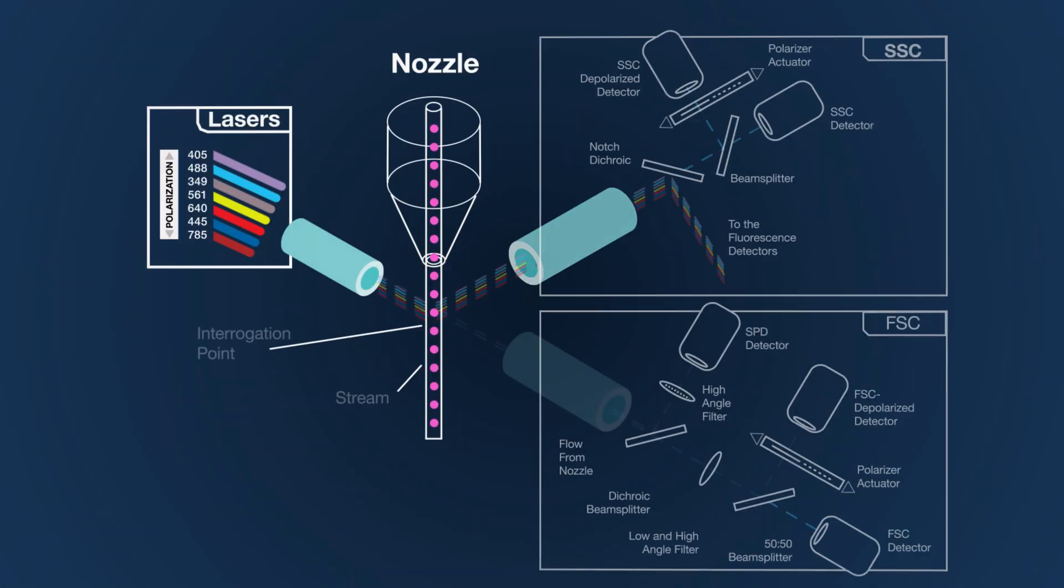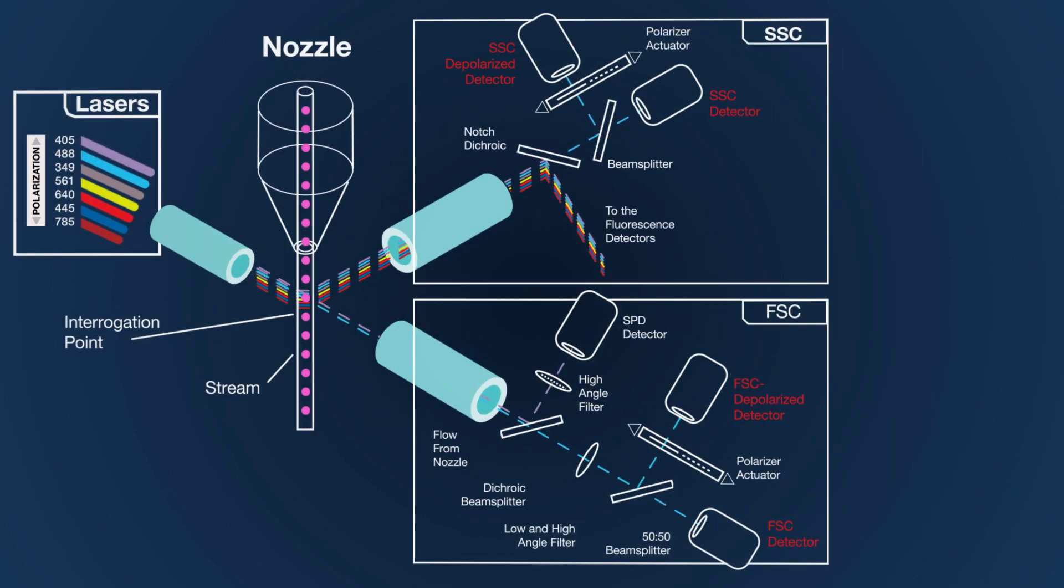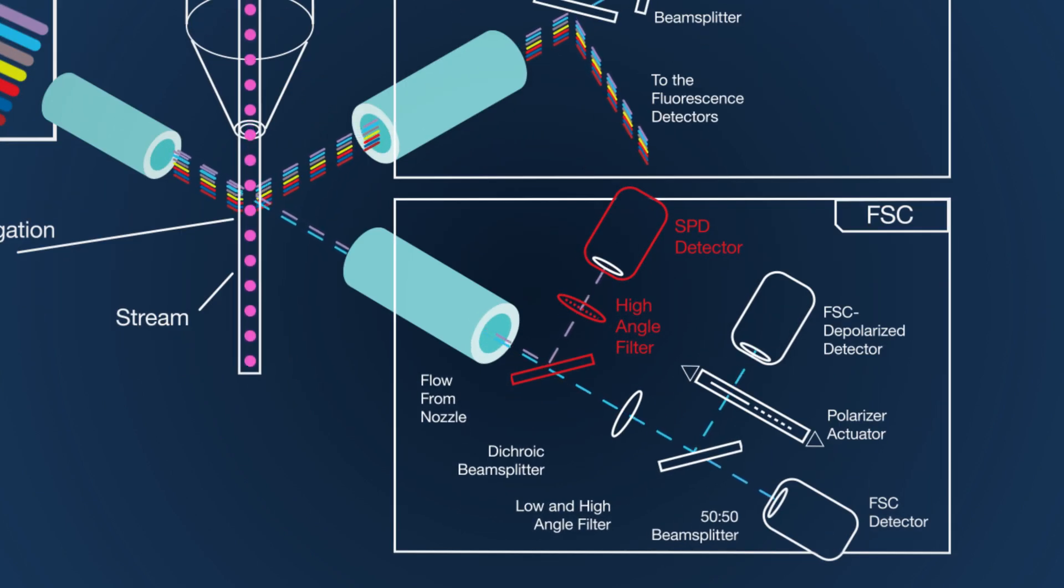Multiple scatter options offer greater flexibility with 488 nanometer forward scatter and side scatter, polarized 488 nanometer forward scatter and side scatter, and small particle detection with a dedicated 405 nanometer forward scatter.